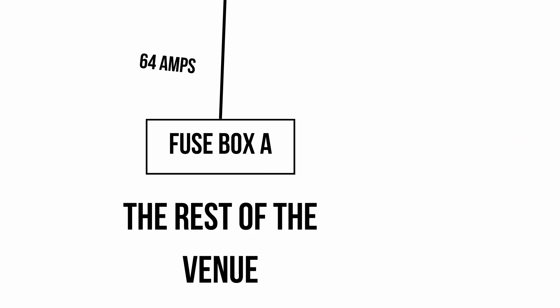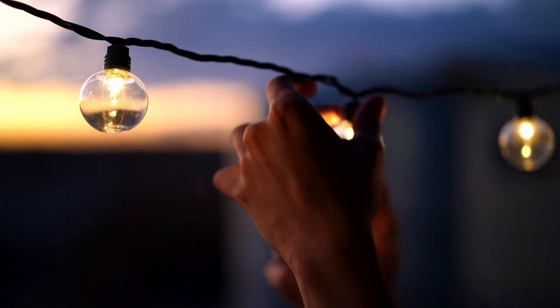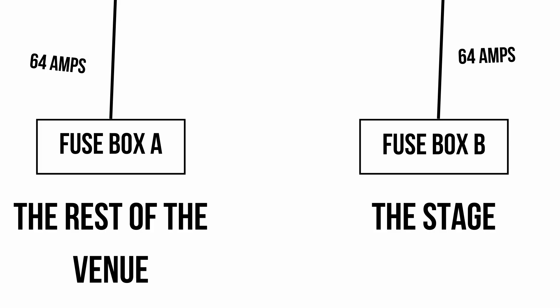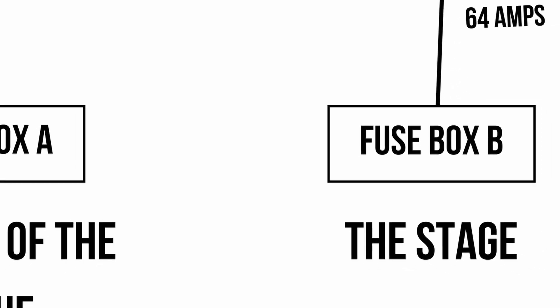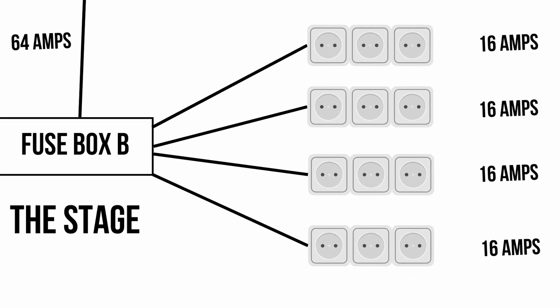Those two 64s go to power cabinets — a circuit breaker panel — where the power is broken down further into several circuits. You might find that one 64 is allocated to the rest of the venue — bar, lighting, that sort of thing — and the other 64 is allocated to the stage. Here in Norway, a regular wall outlet runs at 16 amps maximum, which means with 64 amps available for the stage, you can have four separate 16-amp circuits to connect things to. Think of it like four independent channels on your sound mixer.